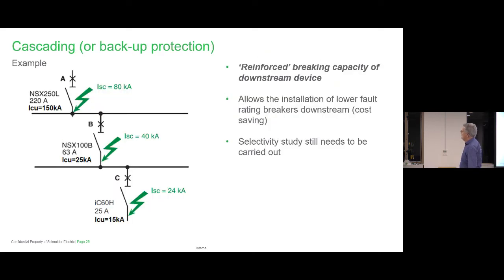This is a nice example of the potential faults that you can get. So I've got a 150 kA capability. It's a current limiting breaker here. We have a 25 kA breaker here, and we have a 15 kA breaker here. But the prospective fault level is higher than the ICU here. In this case, no. At the source, at the beginning, you must have a breaker that deals with a fault at the top, because you've got nothing above it. You've got no cascading happening above this. This is the starting point. So you must have the breaker for the prospective fault you've calculated here. Downstream, all this downstream stuff, this is where you have opportunity to make change.